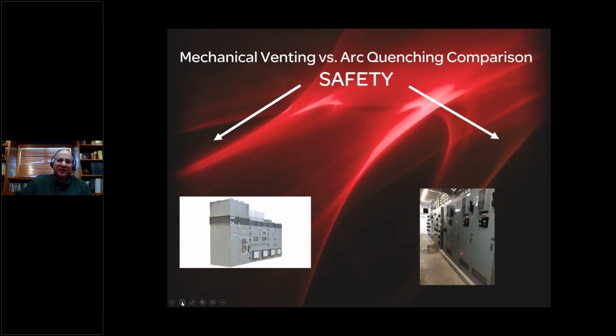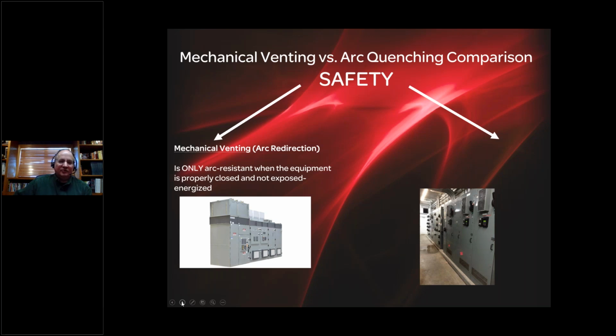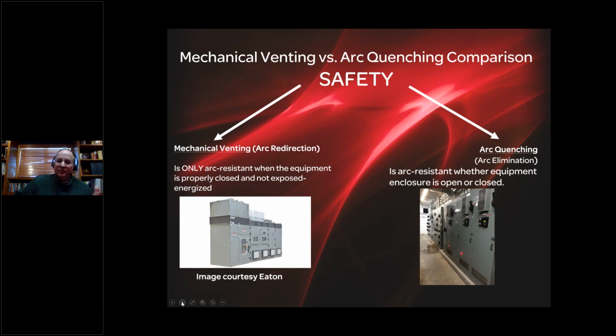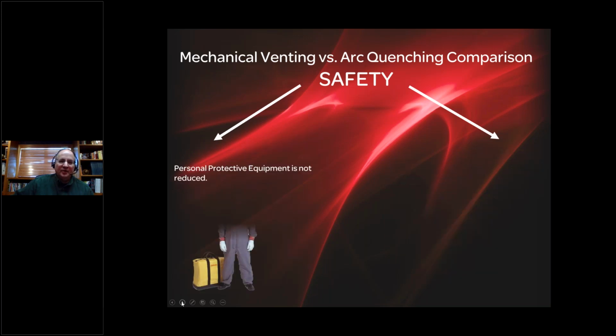So, summarizing mechanical venting versus arc quenching in terms of safety: mechanical venting is only arc resistant when the equipment is properly closed and not exposed energized. Whereas with arc quenching, it's arc resistant whether the equipment enclosure is open or closed. And the picture there shows, again, a large Rockwell VFD lineup that we protected with our arc quenching system.